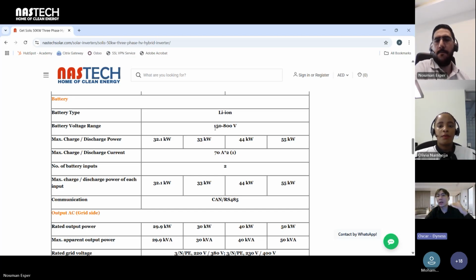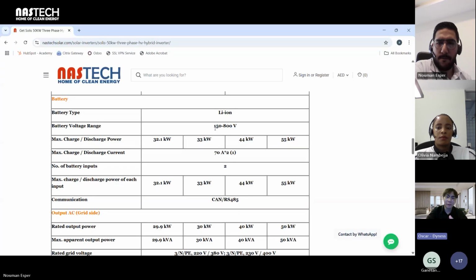If you want to ensure the C rate of charge and discharge, you also have to check the maximum charge and discharge current, because we are using 1C as the maximum charge and discharge rate. So the output current will be 100 ampere. That means for this product, maybe we can only support 0.7C, which is also quite enough for daily use, and also good for a longer lifespan.